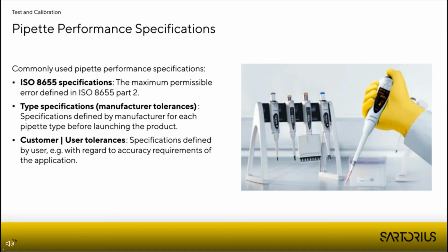As these specs are sometimes really very small, they cannot be reached under all environmental conditions. So when performing a calibration in a normal lab on the customer side, it sometimes is not possible to reach these specifications. And then, last but not least, we do have the performance specifications that are defined by users. And these normally result from the process needs of the customer and the specific application.